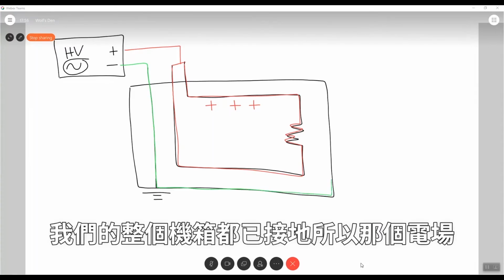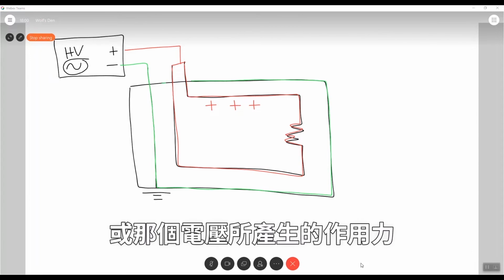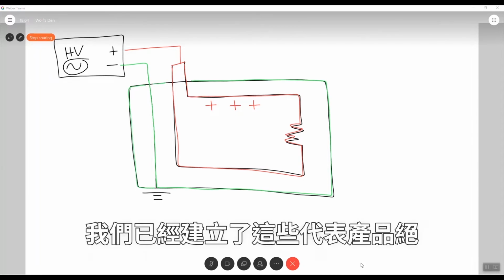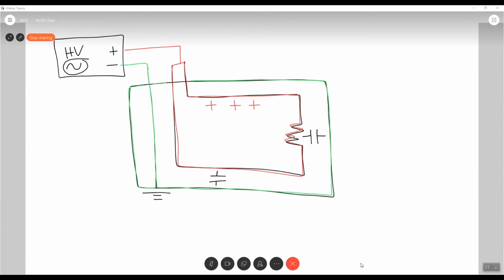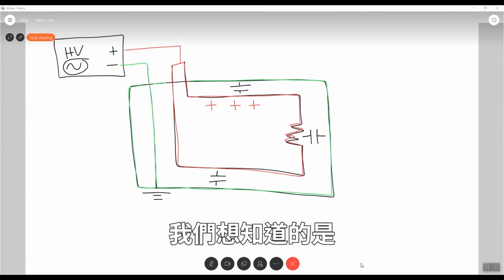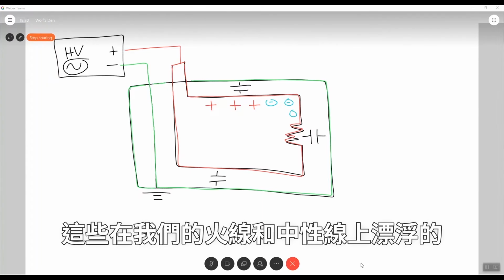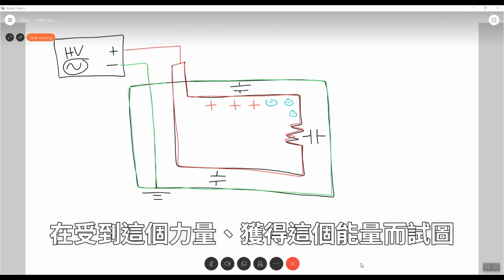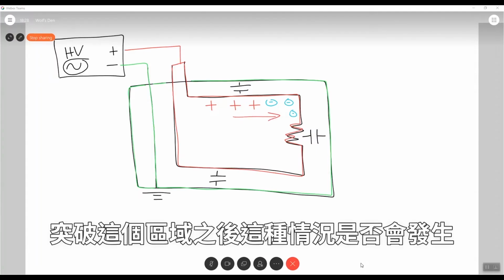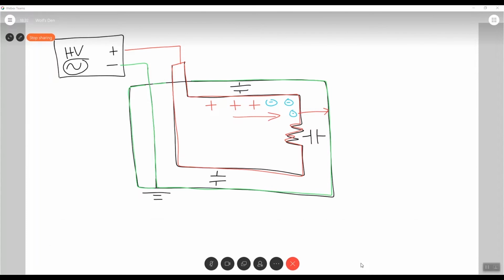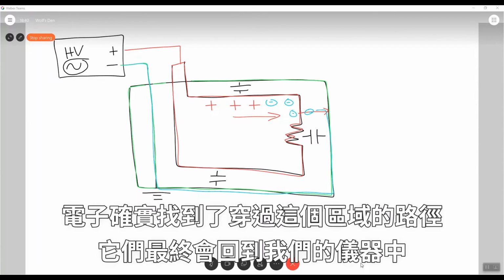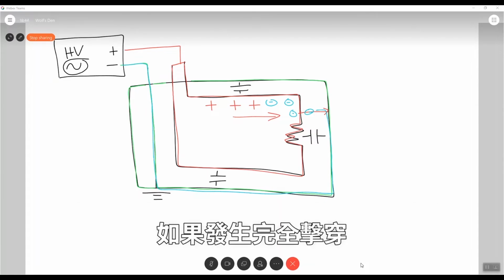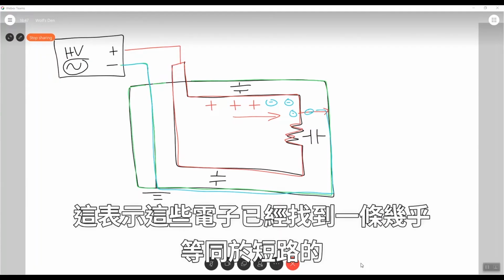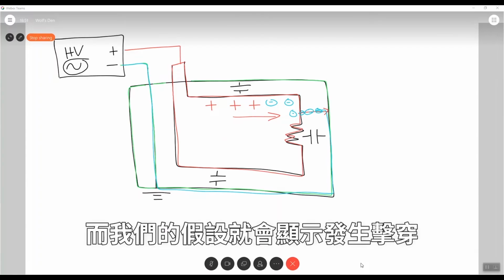Right? Our entire chassis is grounded, so that electric field or that voltage, that force is going to be around our entire DUT. So now we've created these capacitors representing the insulation of our product all around our product. And what we want to know is, will any of these electrons that are floating on our line and neutral, which have now been given this force, this energy to want to break through this area, will that happen? If electrons do find their way through, they will be returned to our instrument and be measured by how much leakage has occurred. Now, if there's a complete breakdown, that means that these electrons have found a path through almost as a short, and our Hipot tester will report a breakdown.